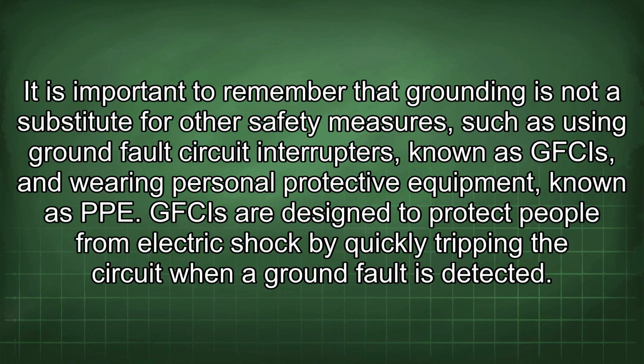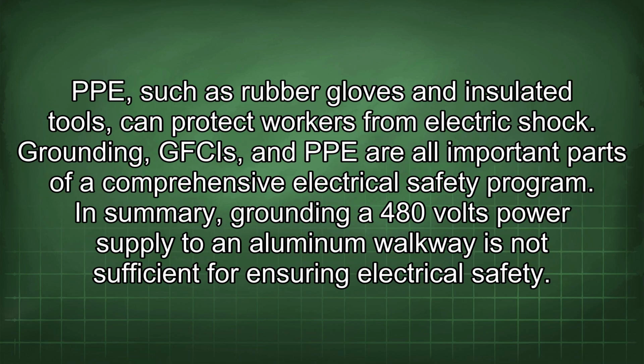It is important to remember that grounding is not a substitute for other safety measures, such as using ground fault circuit interrupters, known as GFCIs, and wearing personal protective equipment, known as PPE. GFCIs are designed to protect people from electric shock by quickly tripping the circuit when a ground fault is detected. PPE, such as rubber gloves and insulated tools, can protect workers from electric shock. Grounding, GFCIs, and PPE are all important parts of a comprehensive electrical safety program.